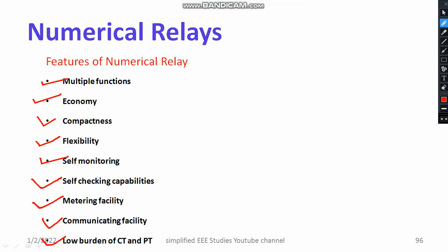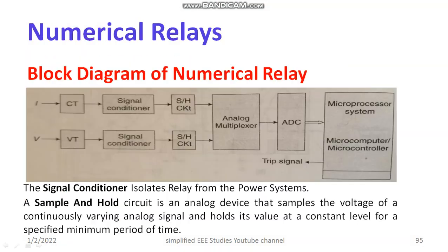So the main component of numerical relay, as we discussed, is microcontroller, or digital signal processor. Based on the program, it is going to operate. So in case of electromechanical relay, are you doing any program? No, there is no program. It will operate based on the electromagnetic attraction, then based on the induction principle. Likewise, some conventional operation will be done in case of electromechanical relay. But in case of your DSP based relay or numerical relay, it works based on the program. It is totally compact compared to electromechanical relay.